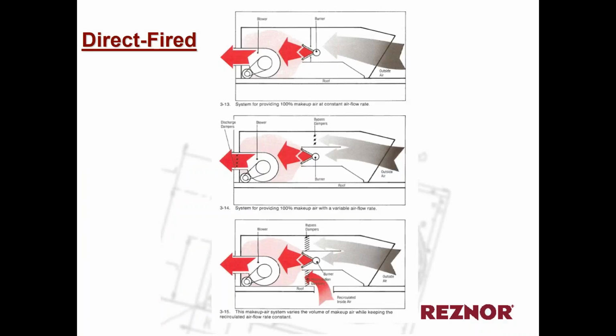And this will just give you a view of what those direct fired units, what the pattern or the layout, the configuration of these units look like. So from the top, we could do just 100% outside air. From the middle there, we can provide a variable airflow rate with 100% outside air. And then at the bottom there, you'll see we can do units that do a combination of some return air with outside air as well.